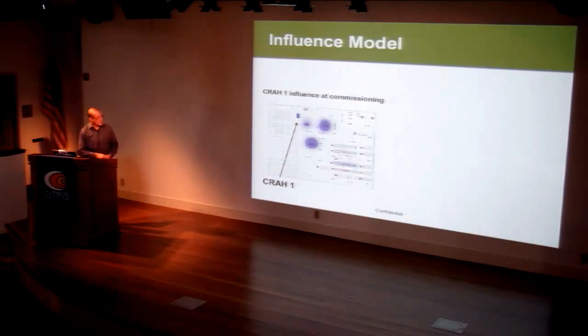You can see actually a little pink right here. What it's predicting is that when this one gets activated, supposedly to cool, it will actually heat up some parts of the data center a little bit. And we see that all the time. Air basically follows the path of least resistance. And if you turn this on, while you may pressurize areas near this unit, you can just as well depressurize other places, and the amount of air coming out of the floor could go down.